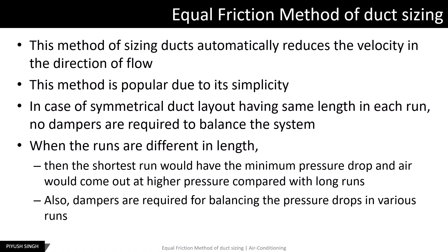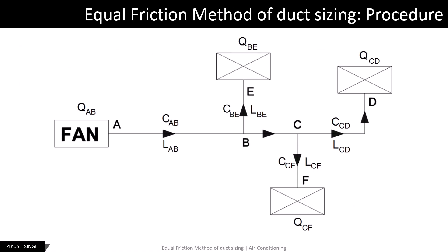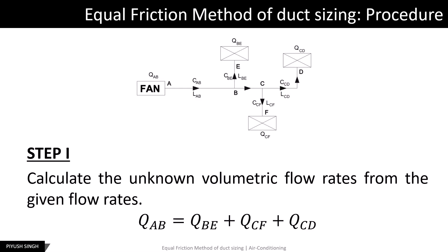Dampers are required for balancing the pressure drop in various runs. This method is not very popular in systems with very long runs. In step 1, the unknown volumetric flow rates are calculated from the given flow rates. The discharge from the fan will be equal to the sum of the air supplied to the different zones due to continuity. Therefore, in this system, Q_AB is equal to Q_BE plus Q_CF plus Q_CD.